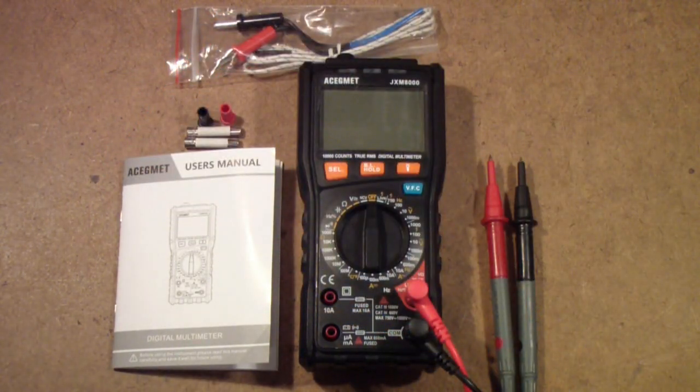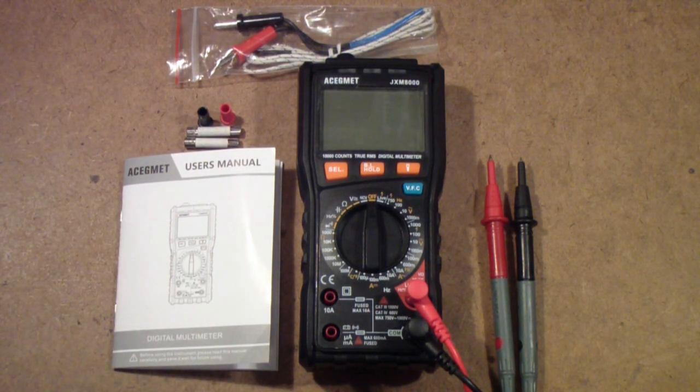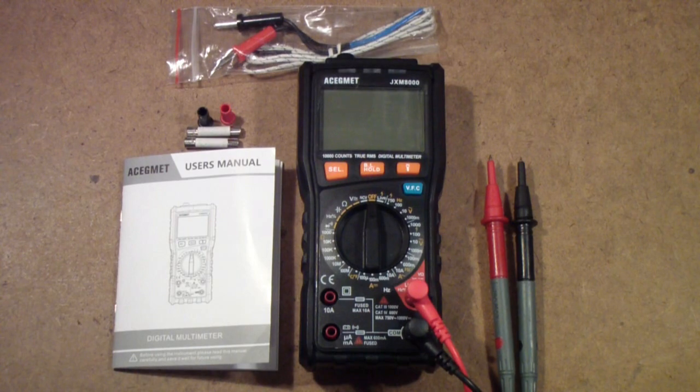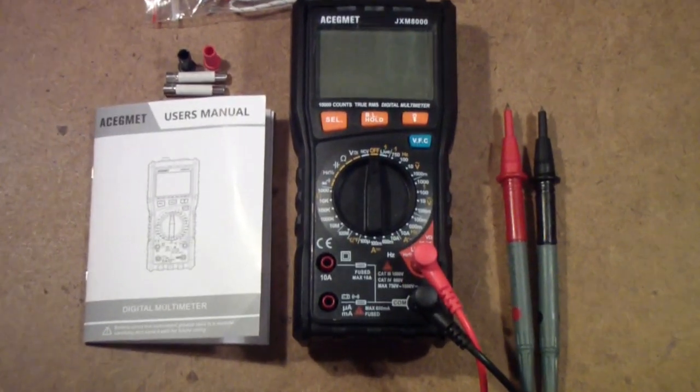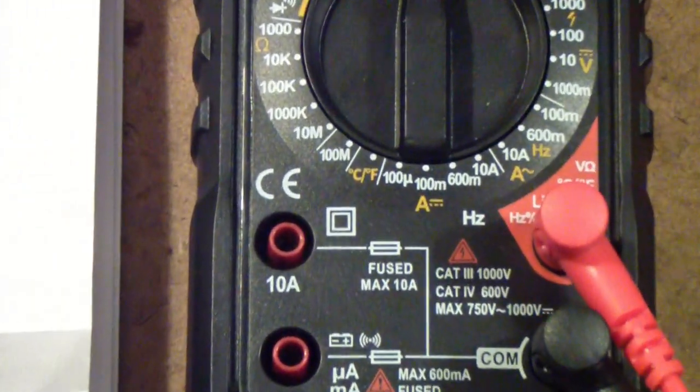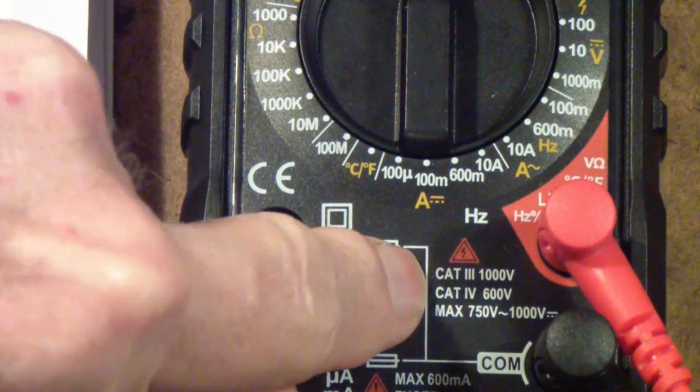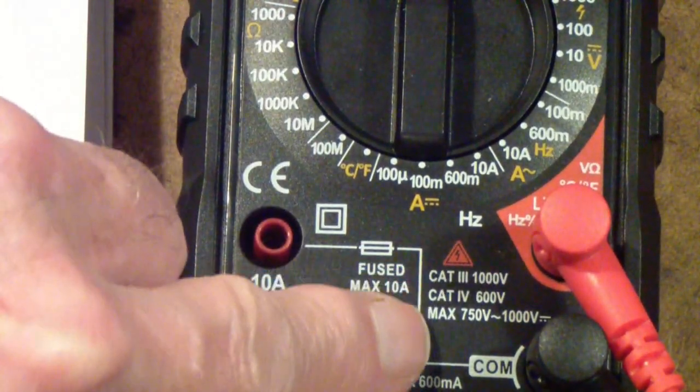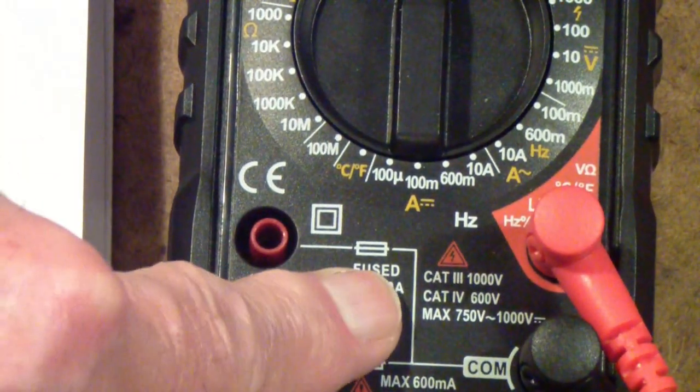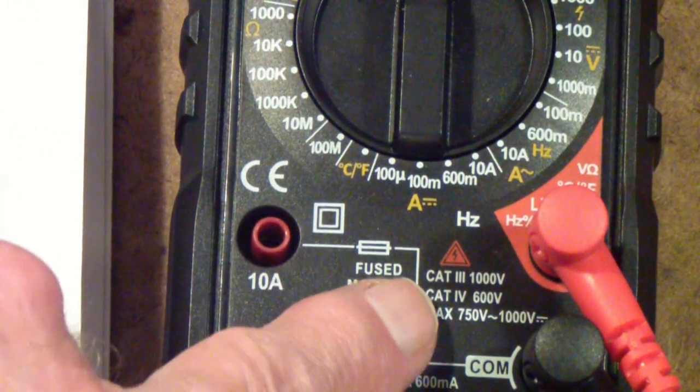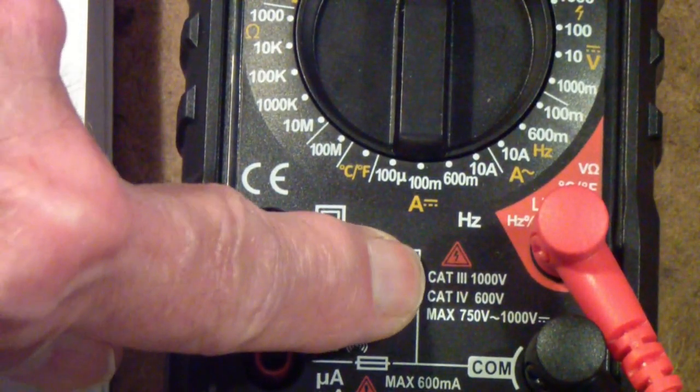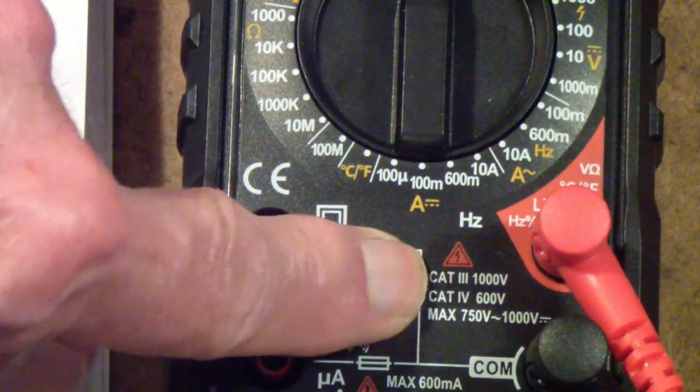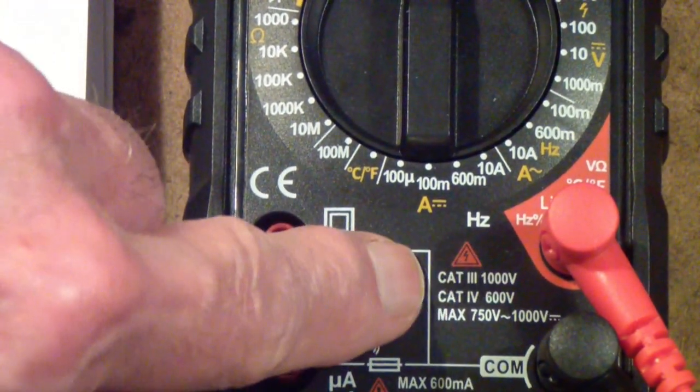If I were working in an environment with concrete floors, especially on a ladder, I would have left this on. The other safety factor you need to think about in terms of your environment is what kind of equipment are you going to be working on. You'll notice right here it says CAT 3 1000 volts, CAT 4 600 volts, with a max of 750 volts and 1000 volts. These CAT ratings refer to the relative protection the meter provides. CAT 3 is sort of the standard best today—there was a CAT 1, I don't think anybody makes CAT 1s anymore, there was a CAT 2, and then CAT 3.